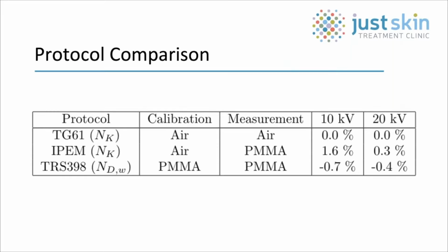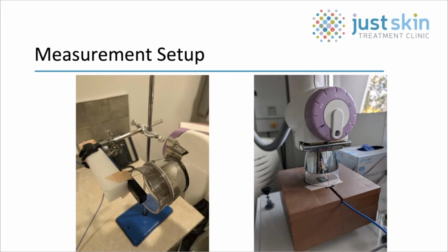There is a recommendation document by the Swiss Society of Radiobiology and Medical Physics, which I highly recommend for anyone wishing to use the TRS-398 or German DIN protocols. Here are some photos of my measurement setup, both in-air and in-phantom measurements. The equipment shown in these photos is the same as used for other energies. The in-air method has the advantage that the exact same calculation as the higher energies can be used. However, alignment of a thin window chamber in air is much more difficult than a cylindrical chamber, as a small rotation in the chamber results in a distance offset. Meanwhile, the in-phantom method has the advantage of being a much easier and reproducible setup.